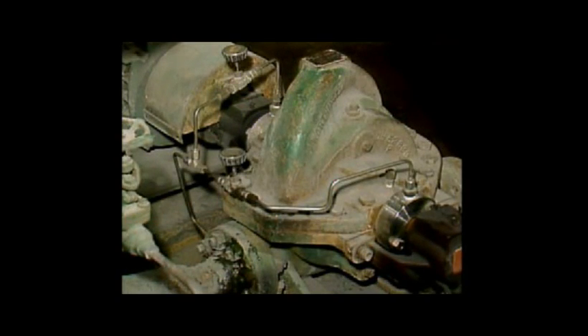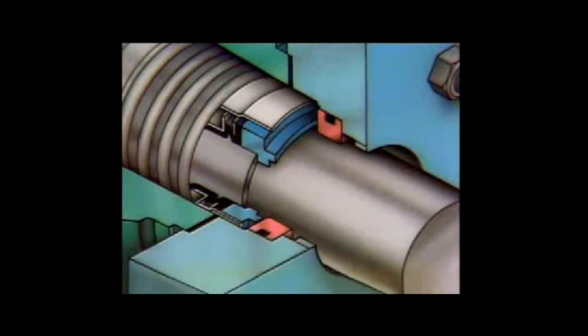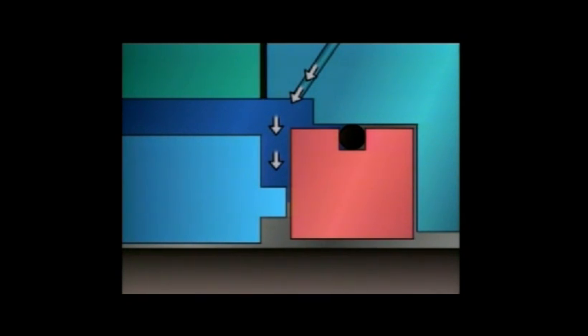Another way to seal between a pump's shaft and its casing is to use a mechanical seal. Mechanical seals do the same basic job as packing, but they provide a more complete seal. A mechanical seal has two elements — a stationary element and a rotating element — each with a seal ring. The seal rings mate together to form a nearly perfect seal with virtually no leak-off. To prevent the seal rings from drying out, overheating, and becoming damaged, some type of lubricant must be supplied. In some applications the liquid being pumped is used as the lubricant; however, if the liquid contains abrasives or would be hazardous if the seal failed, an external source of clean liquid may be used.